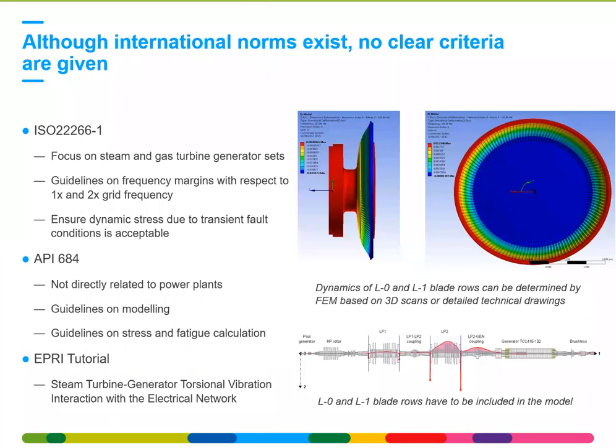On the right, you can see an example, for instance, as well, of the ISO standard: the frequency margin also holds for the steam turbine blades. So here, typically, the last and prior to last blade rows have to be included in the torsional vibration model to check whether there's any dynamic coupling between the rotor and the steam turbine blades. If these have natural frequencies close to once or twice grid frequency, you could as well induce excessive torsional vibrations of the blades and induce crack initiation at the roots where the highest stress occurs. So this is typically checked by means of finite element simulations based on a scan or detailed geometry of the blade and then included within the torsional vibration model.